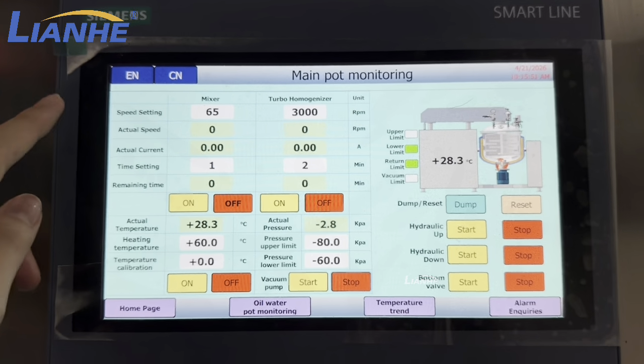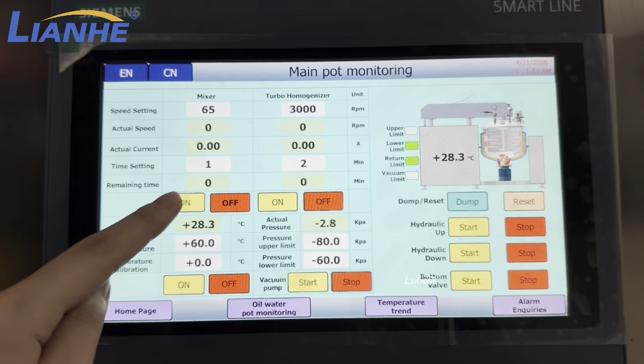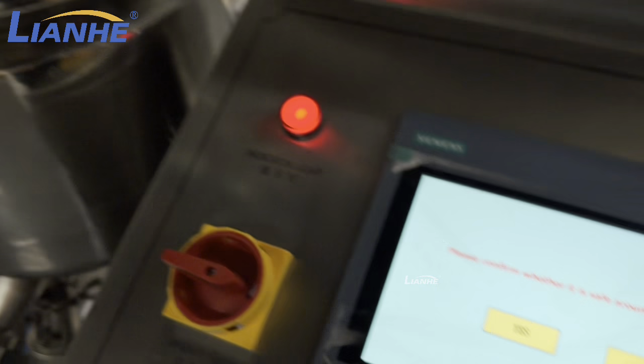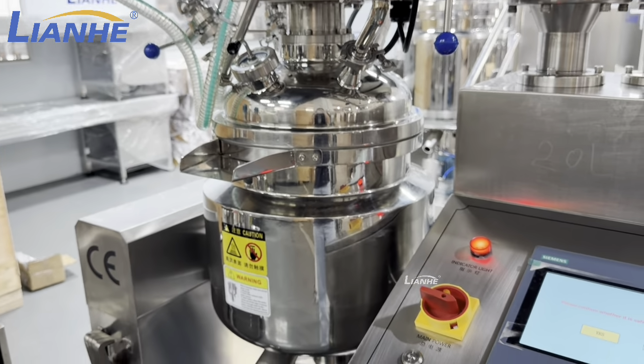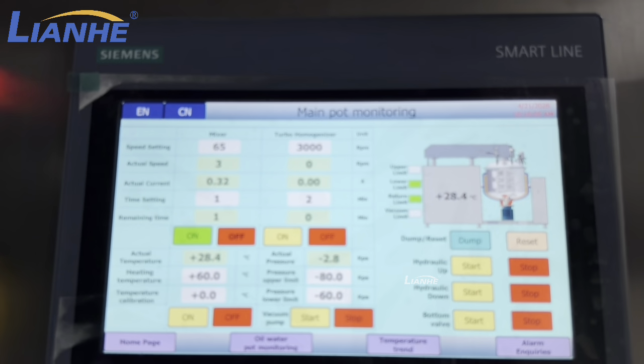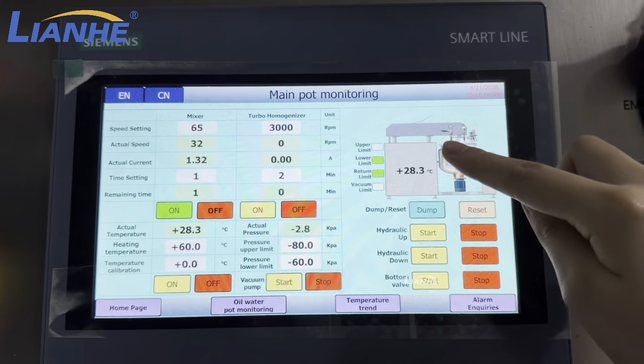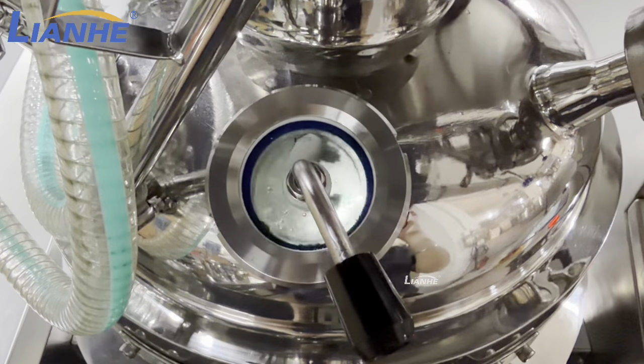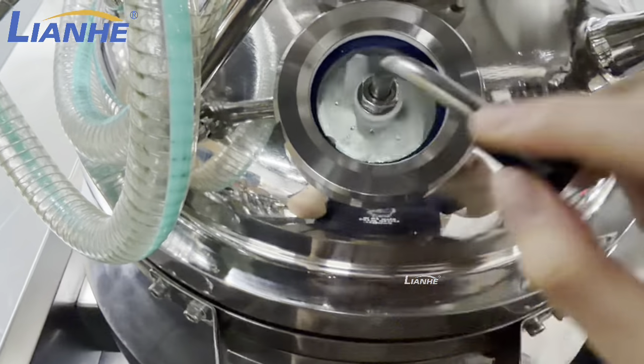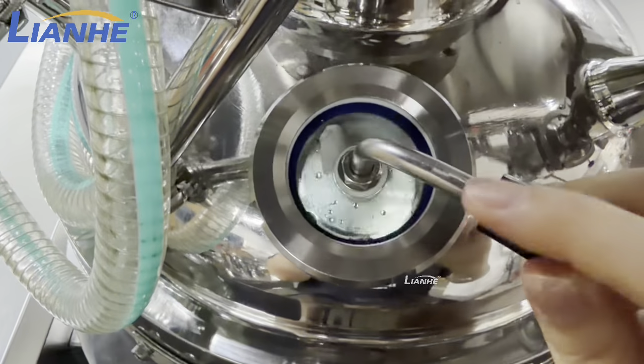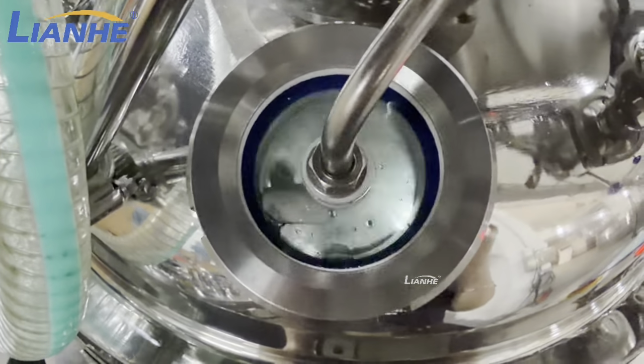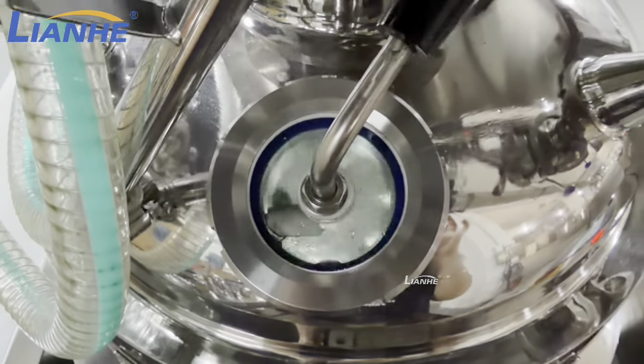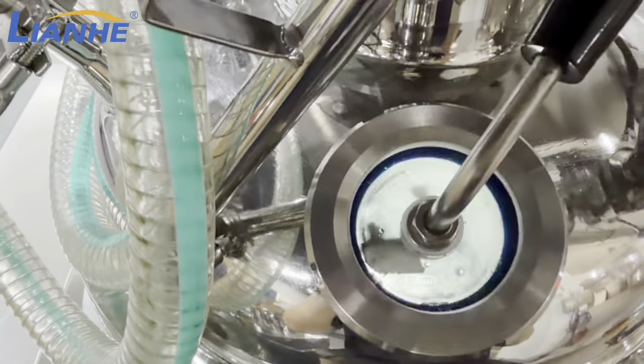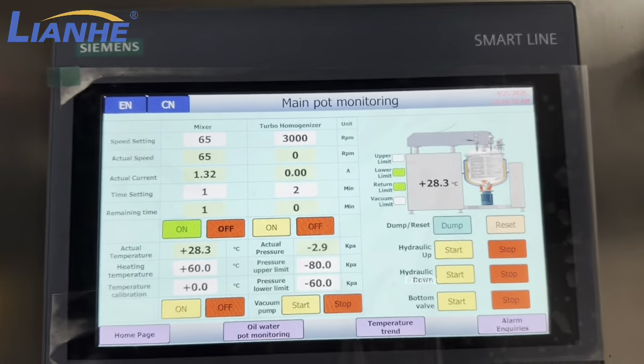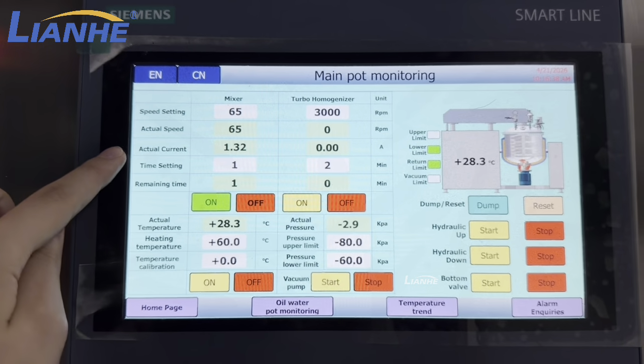We have already set the speed 65 and the time 1 minute. Turn it on, confirm that it's safe around the main tank. And then turn it on. And you can see the diagram is also moving. Let's check inside. You can move this to check the clarity inside the tank. And now the actual speed is 65. The actual current you can check here.